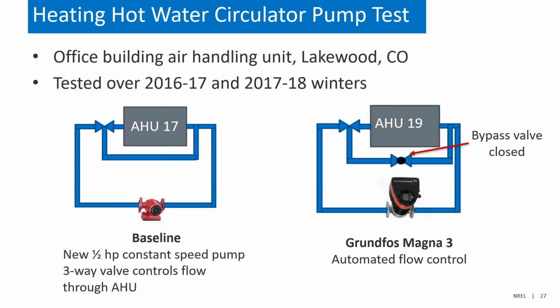For these, they're air handling unit booster pumps. You can see the way that they're configured is you essentially have a 3-way control valve that diverts water around the heating coil when that valve starts to close off. So again, when these units turn on, the pump power stays constant throughout the operational period.